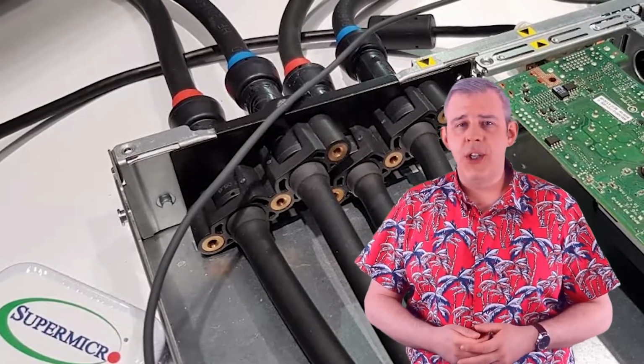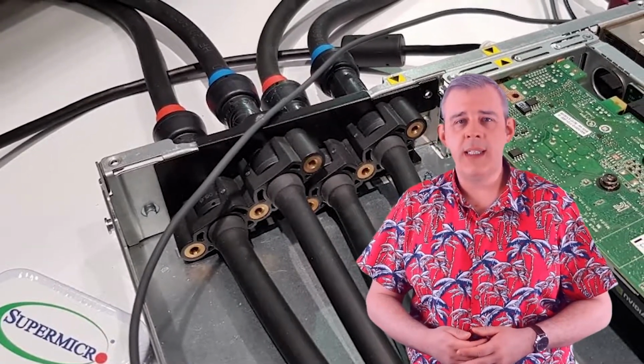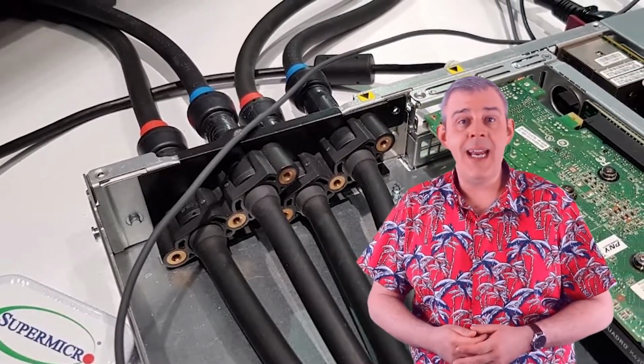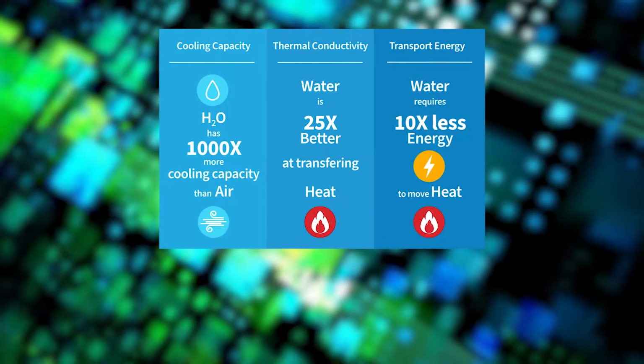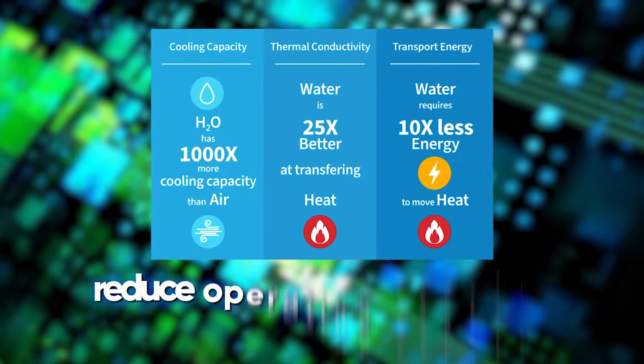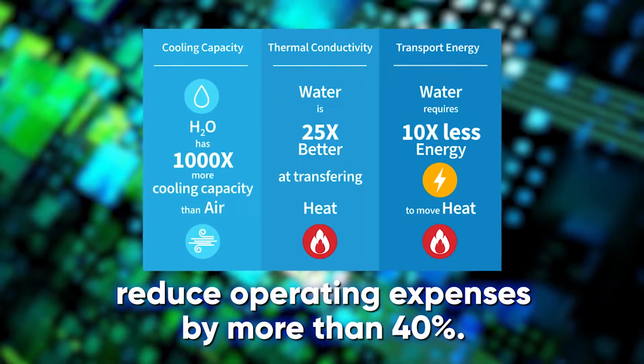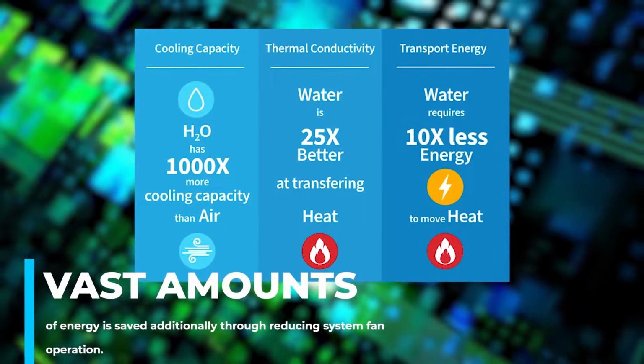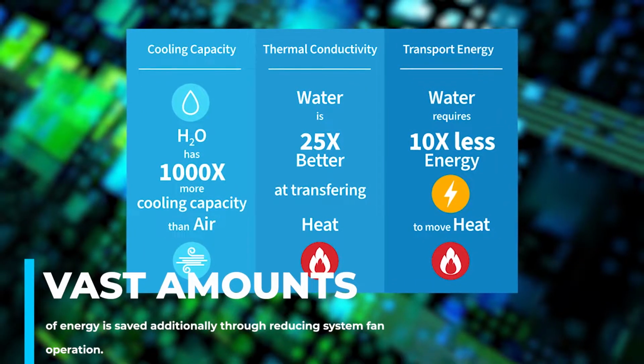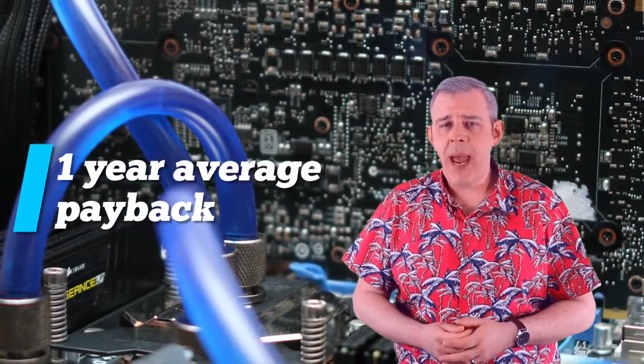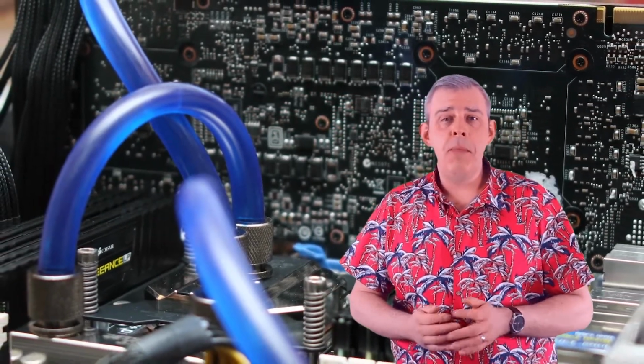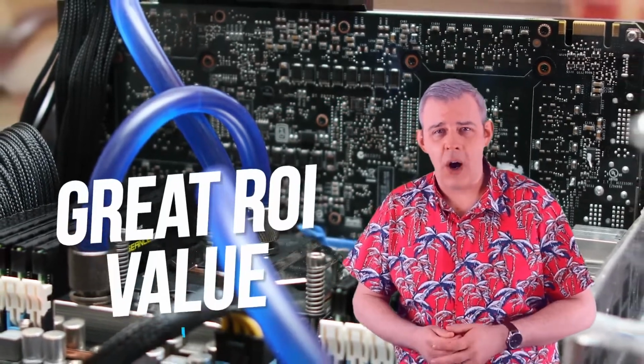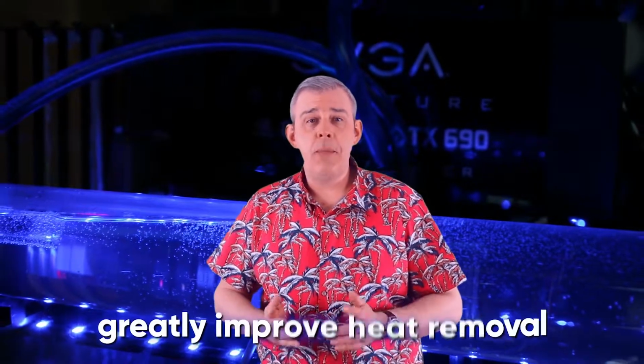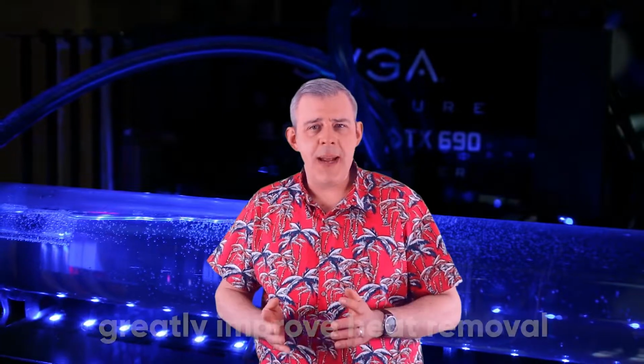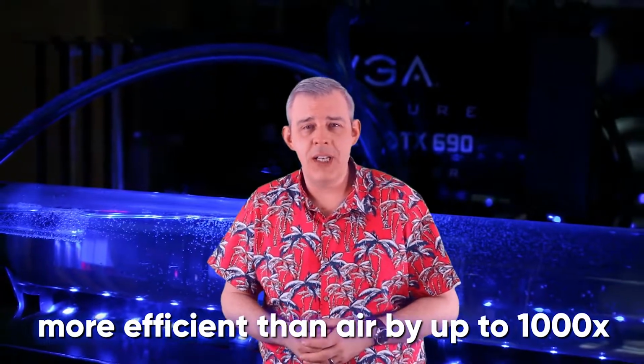All of the aforementioned solutions support Supermicro's liquid cooling systems, greatly improving their efficiency in any application. By switching from air conditioning to liquid cooling, you could reduce operating expenses by more than 40%. Vast amounts of energy are saved additionally through reducing system fan operation. On average, you can see a 1-year average payback on facility investment, giving Supermicro's liquid cooling solution a great ROI value. Not just financially can liquid cooling benefit you—it can greatly improve heat removal, with liquid being fundamentally more efficient than air by up to 1,000 times.